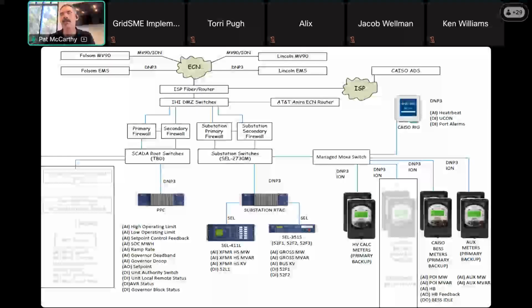You can expect CAISO to ask you to simulate each of the points listed on this document from the originating device. To walk you through what a point-to-point test looks like, usually we start with meters, because in addition to being revenue devices, meters are also telemetry devices. The revenue component of the test involves loading the meters up with data from a test set, so CAISO can reconcile their revenue billing system with their telemetry system.